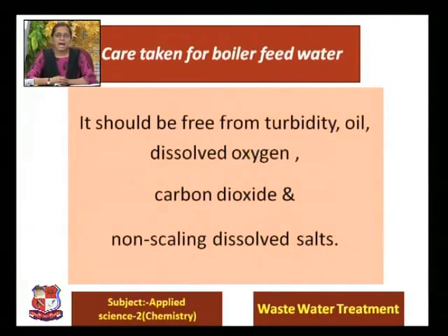What care do we have to take whenever we use water in the boiler in industries? We have to take care that boiler feed water should be free from turbidity, oil, dissolved oxygen, carbon dioxide and non-scaling dissolved salts. This one has to be kept in mind whenever you use boiler feed water.